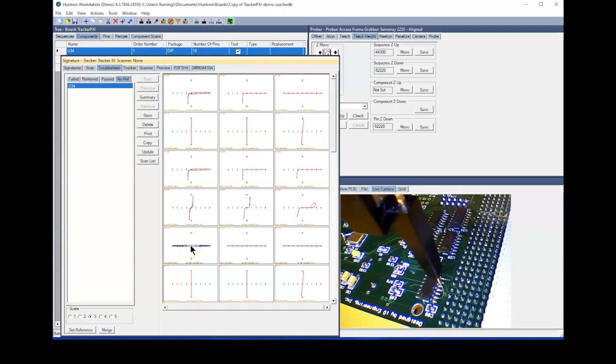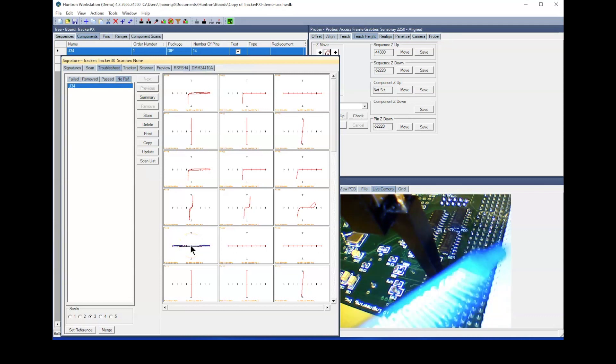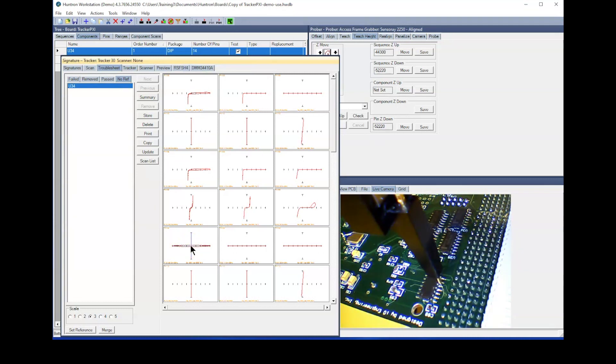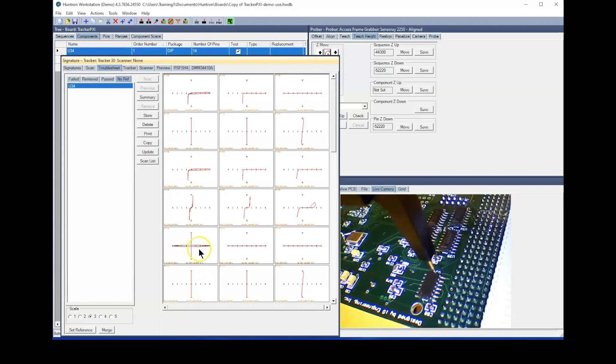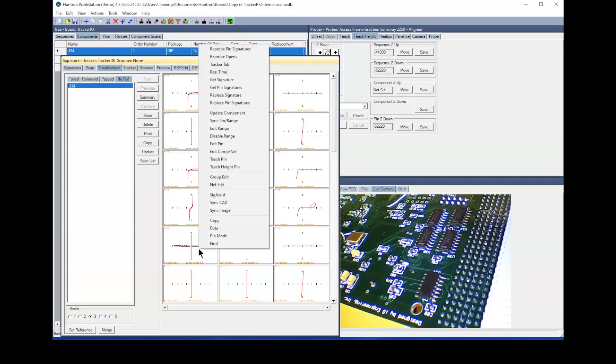This provides you the opportunity to give the probe a little assistance in getting through the conformal coating. A light tap on the side of the probe holder may help the probe tip make contact. If you get the signature you need, right-click and select Replace Signature.